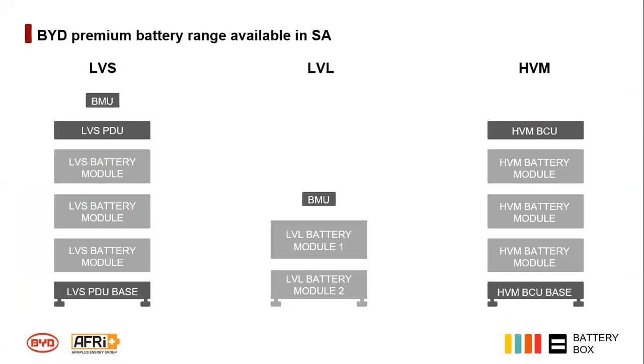So here we've got the bits that make up your batteries. On the LVS we can see the base, battery modules, and the PDU. You can have between 1 and 6 modules per tower on the LVS, and it sits on the base just like Lego, plugs in, and the PDU plugs in on top. There are no other wires between the modules, and no dip switches to set battery addresses — it's just plug and play.